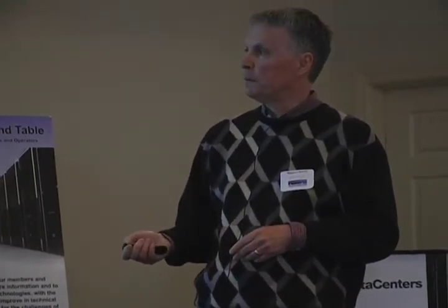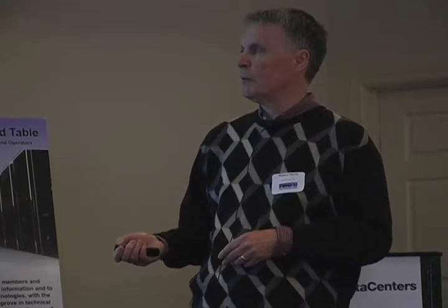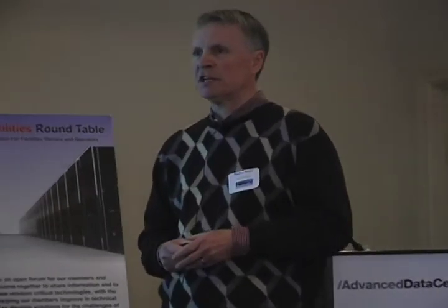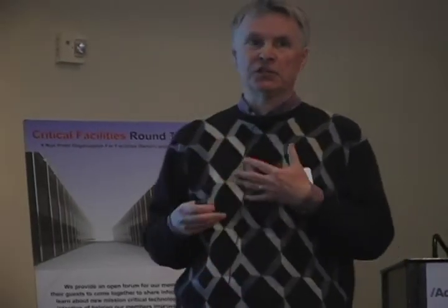Now, just keep in mind that if you're raising your supply temperature too much, you might run into a situation where the servers actually ramp up the internal fans because the intake temperature to that server is a little bit on the high end. And most servers today have two-step fans or variable speed fans. So they might gear up, and they will then consequently draw more electric power. So that's a drawback. Next, please.